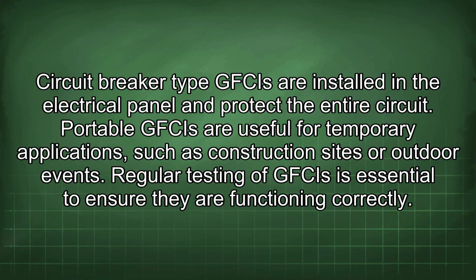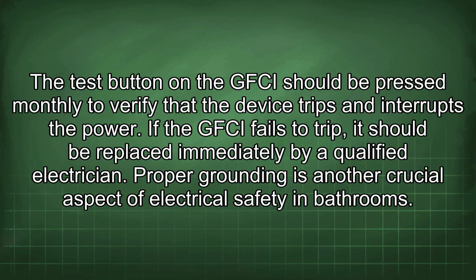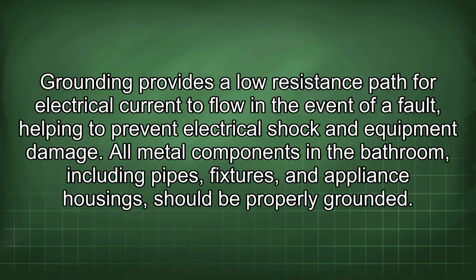Regular testing of GFCIs is essential to ensure they are functioning correctly. The test button on the GFCI should be pressed monthly to verify that the device trips and interrupts the power. If the GFCI fails to trip, it should be replaced immediately by a qualified electrician. Proper grounding is another crucial aspect of electrical safety in bathrooms. Grounding provides a low-resistance path for electrical current to flow in the event of a fault, helping to prevent electrical shock and equipment damage. All metal components in the bathroom, including pipes, fixtures, and appliance housings, should be properly grounded.